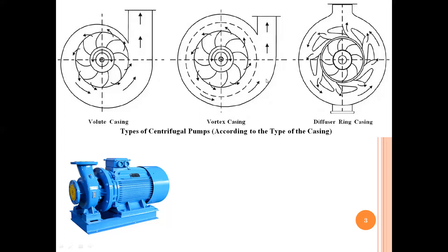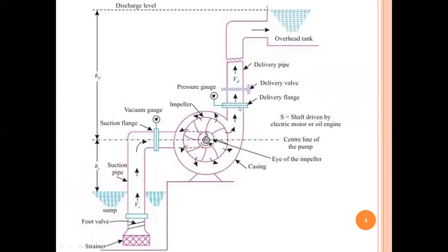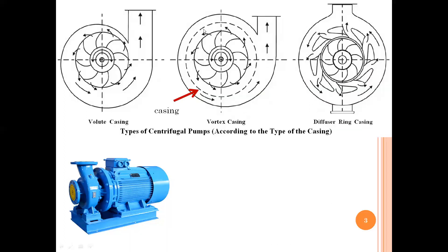The improvisation of the volute casing is your vortex casing. In vortex casing, you have your normal casing, and inside that, you are introducing one more casing inside. As the motor is switched on, water comes through the inner casing — there is no flow in the outer direction. It flows out and comes up. This prevents too much water on the outside, and compared to your volute casing, your vortex casing has a better efficiency.